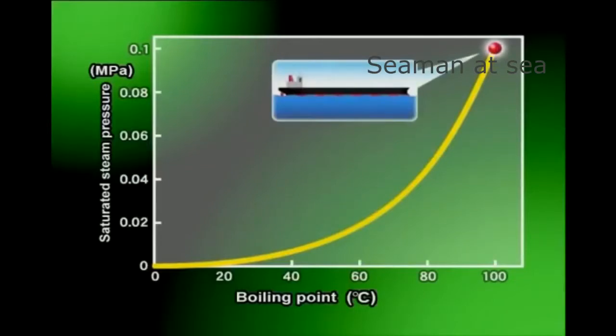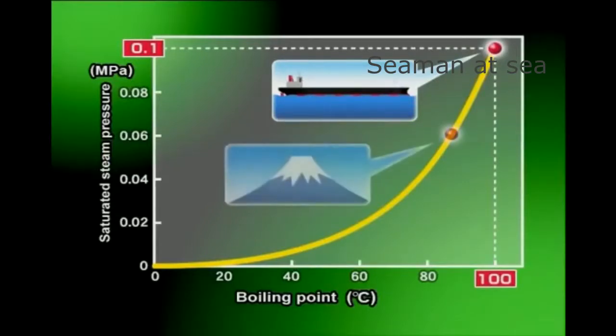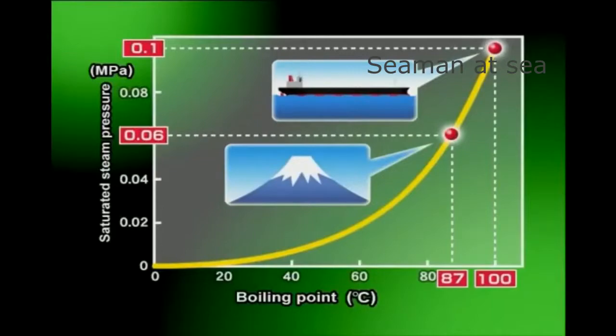Water boils at 100 degrees Celsius under one atmosphere or 0.1 megapascals. But on top of Mount Fuji, the atmospheric pressure drops to 0.06 megapascals, causing water to boil at 87 degrees Celsius. The critical pressure at which a liquid begins to boil under a certain temperature is called saturation vapor pressure for that temperature. The lower the saturation vapor pressure, the lower the boiling point. In other words, vapor bubbles and cavitation occur where water pressure is low.